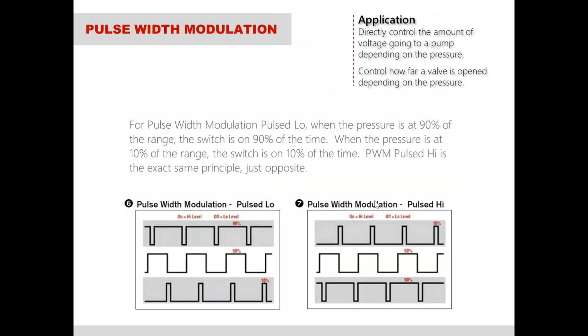The next 2 is pulse width modulation. So the way pulse width modulation works is the switch will actually pulse on and off. And so you can basically use the switch as a transmitter by utilizing this pulse width modulation method. This is a way that people used to use switches to get a continuous output. So for example, if the pressure is at 50% of the range, the switch will modulate or pulse for 50% of the time. If the pressure is at 90% of the range, the switch will pulse on 90% of the time.